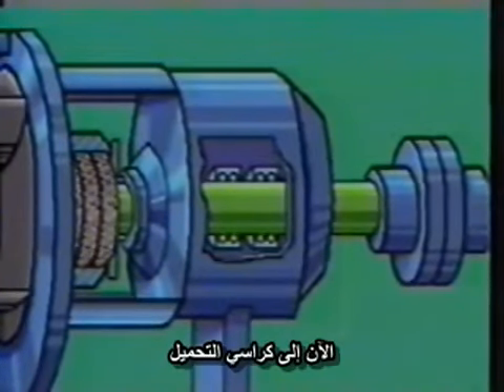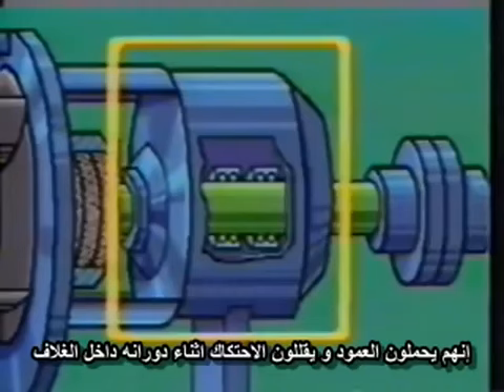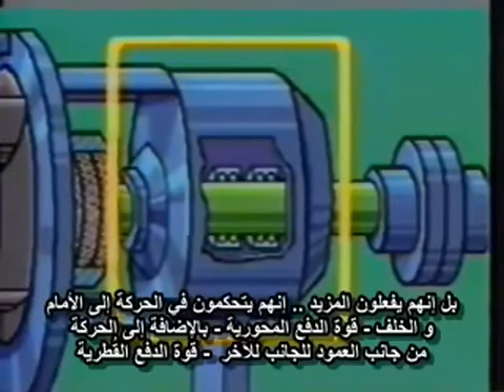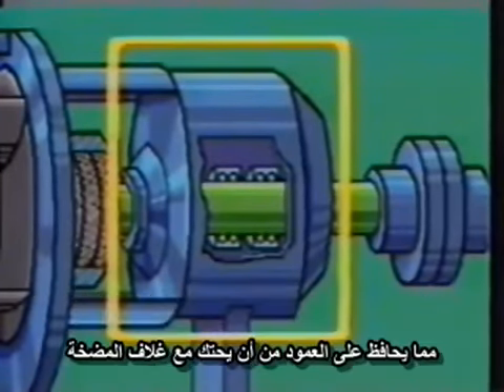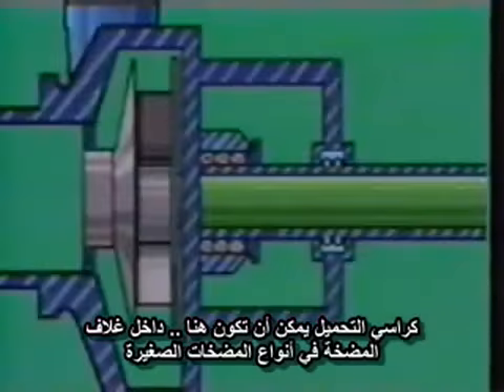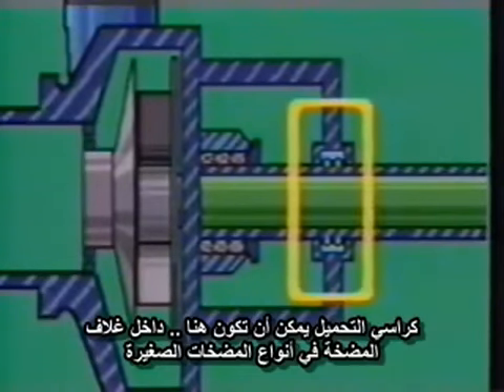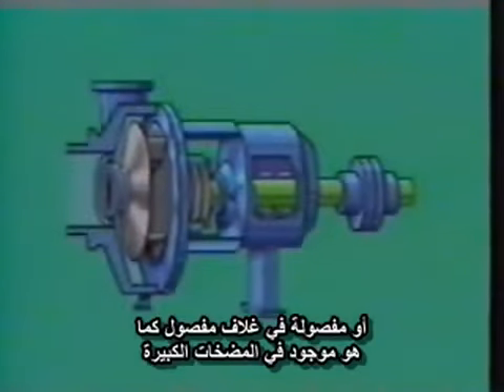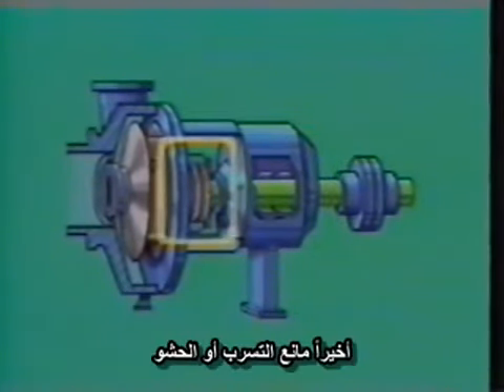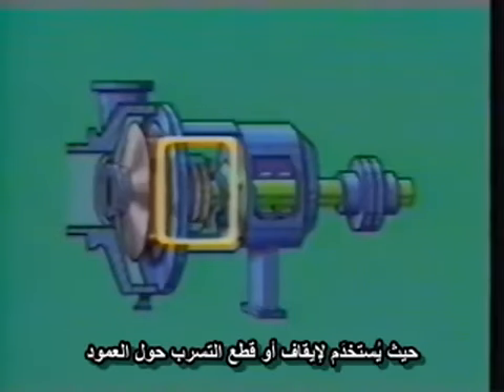Now to bearings. They support the shaft and reduce friction as it rotates in the casing. They do even more. They control the forward and backward movement, the thrust of the shaft, as well as the shaft side-to-side or radial movement. That keeps the shaft from rubbing against the pump casing. Bearings can be here, in the pump casing on small process pumps, or separated in special housings on larger ones. Last are seals or packing. They're used to stop or cut fluid leakage around the shaft.